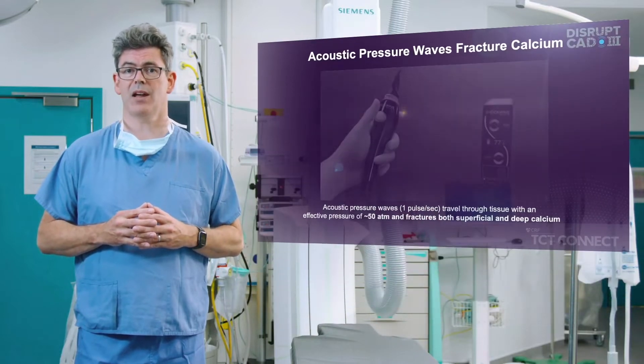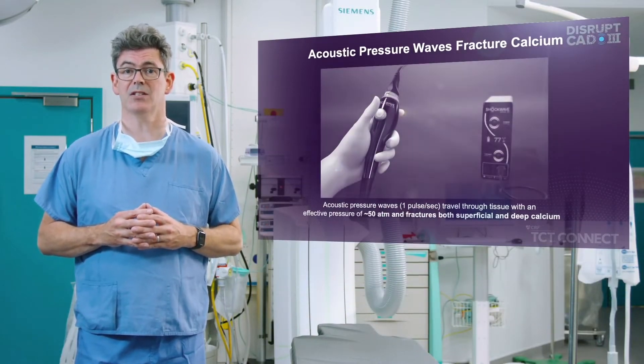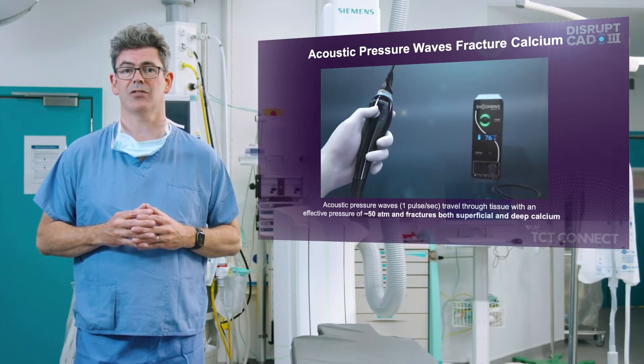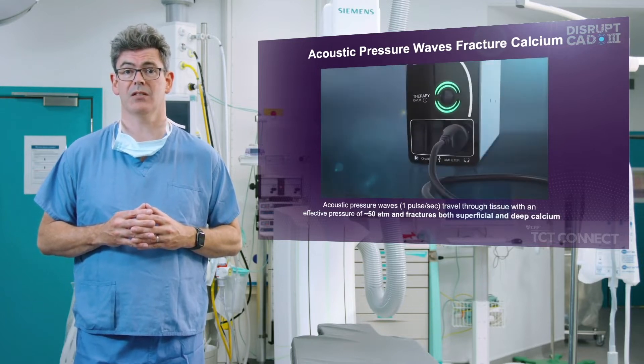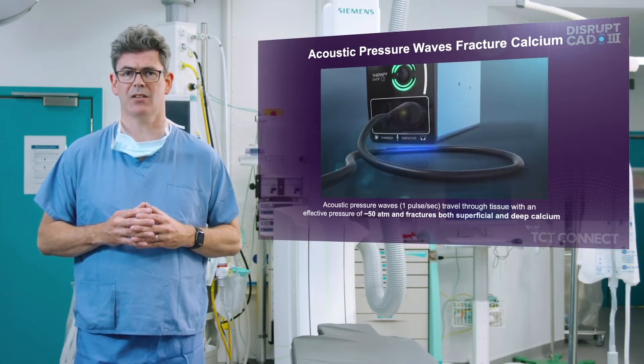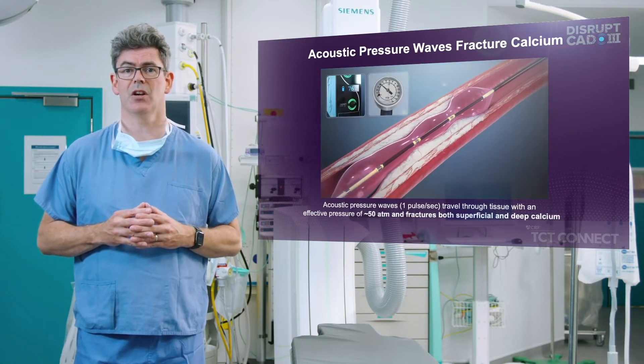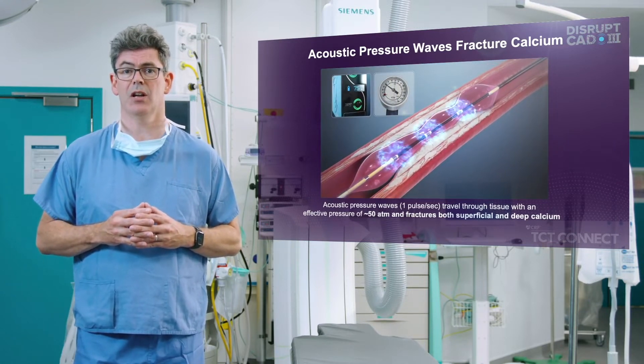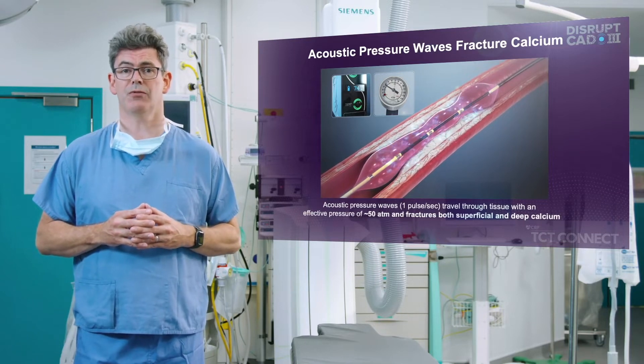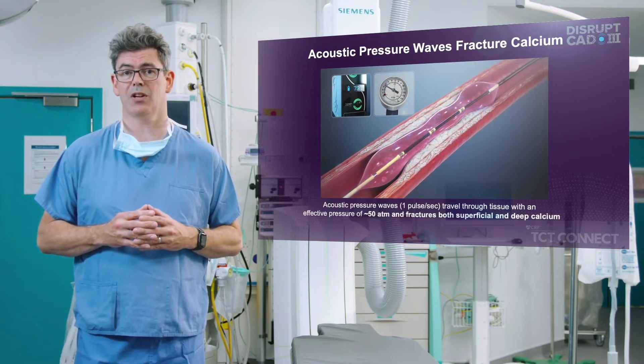Intravascular lithotripsy applies technology that has been used for over 30 years to treat kidney stones. Acoustic pressure waves are generated from emitters placed on the shaft of the balloon angioplasty catheter at one pulse per second, each lasting a microsecond and transmitting up to 50 atmospheres of instantaneous pressure to the intimal, superficial and deep medial calcium.